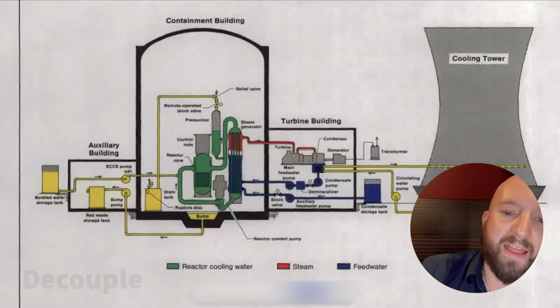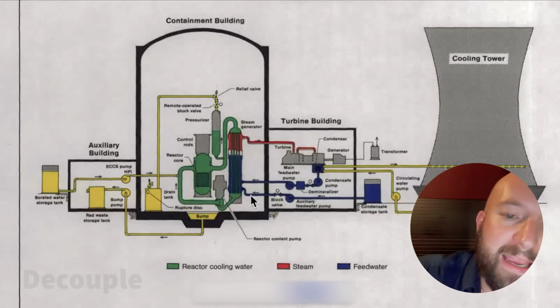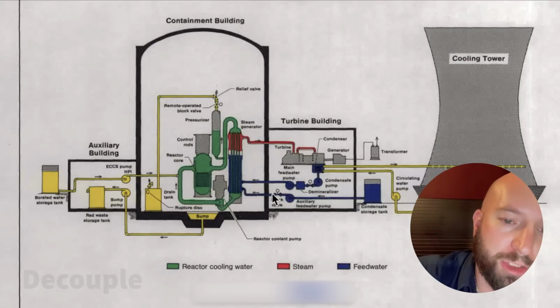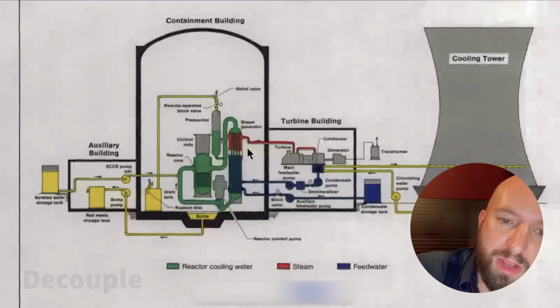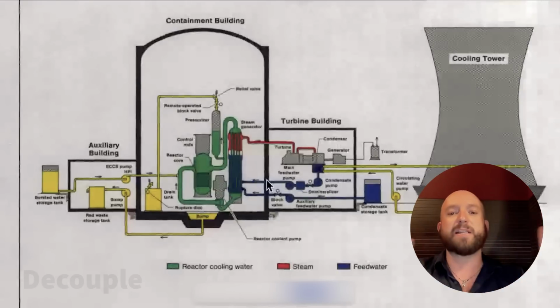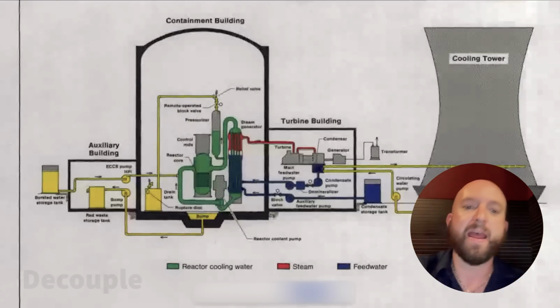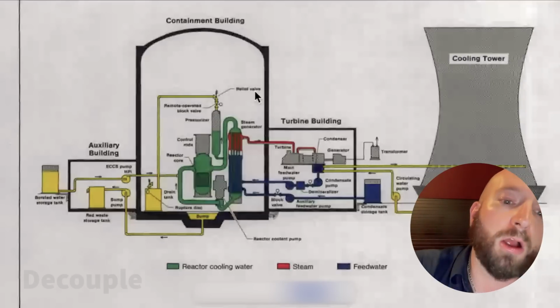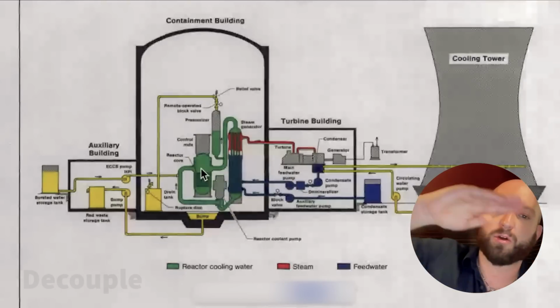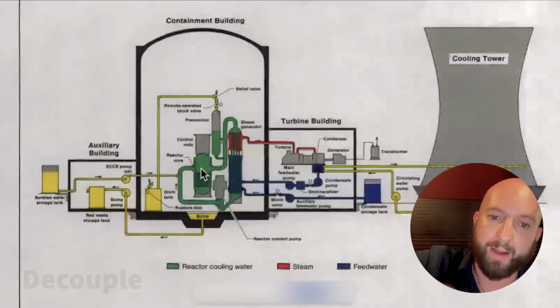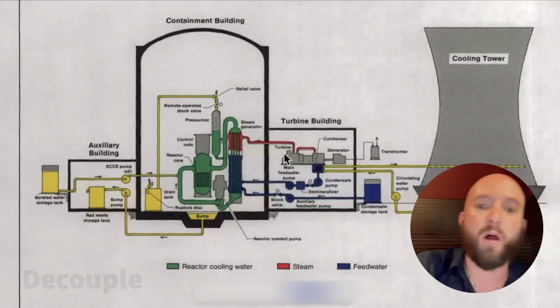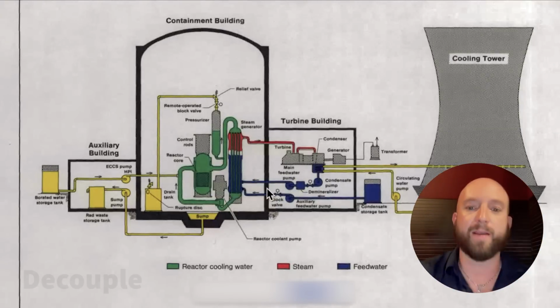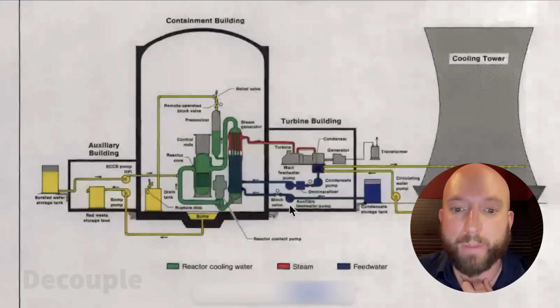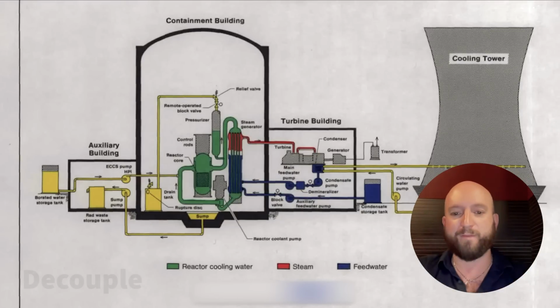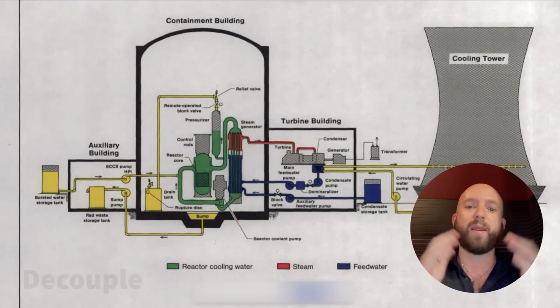And the idea here is that this continuously pumps water into the steam generator, such that even with this reactor coolant pump shut down, natural circulation through the reactor coolant system is enough to take away all of that decay heat and keep the reactor core covered, and the reactor coolant slowly cooling down, right? The RCS slowly cooling down. So that auxiliary feed water pump, as designed, automatically spun up right as that main feed water system shut down. But here's the problem.